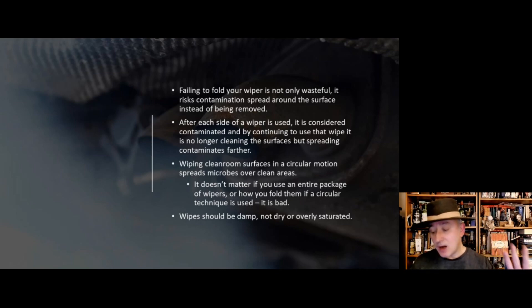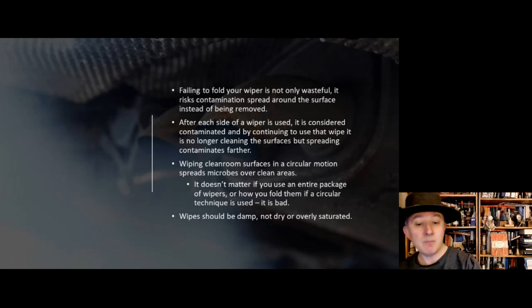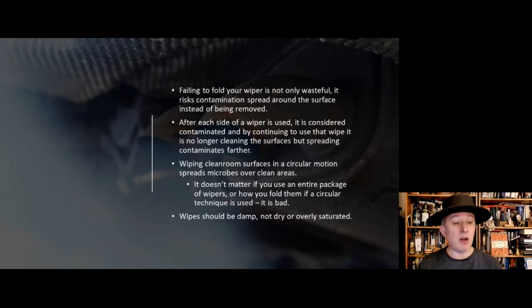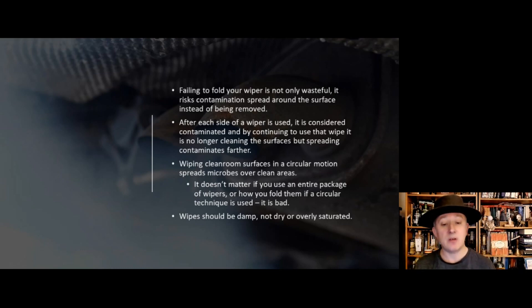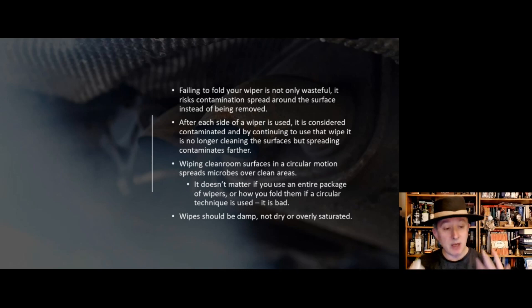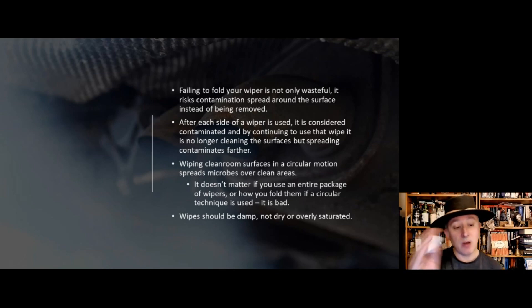We must never apply a clean room wipe in a circular motion. It doesn't matter if you use an entire packet of wipes — circular motion just spreads contamination and may not clean the surface at all. Wipes should be damp but not dry; completely dry wipes are pointless. We also don't want wipes to be completely saturated, as that will impede the ability to achieve the right surface tension.